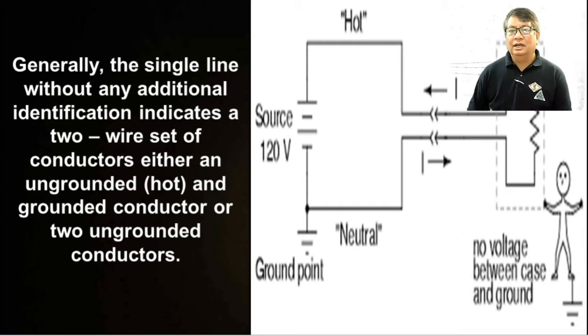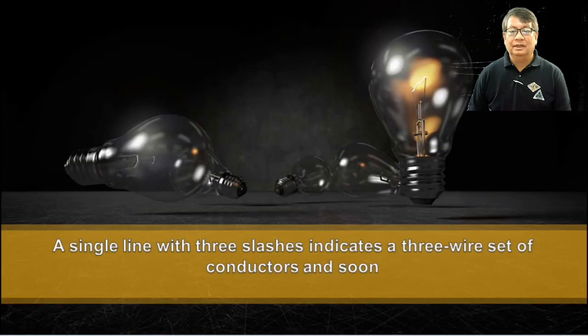So yung unang-una natin dito, we have the source. Okay, we have this ground point. By the way, this is 120. Here in the Philippines, we are using 230. So we have this neutral, and this is the live, because this is line to ground. So you have this line here. Okay, so we have our load. No voltage between case and ground. There should be no voltage between the casing of our load and the ground, para walang short circuit na mangyayari.